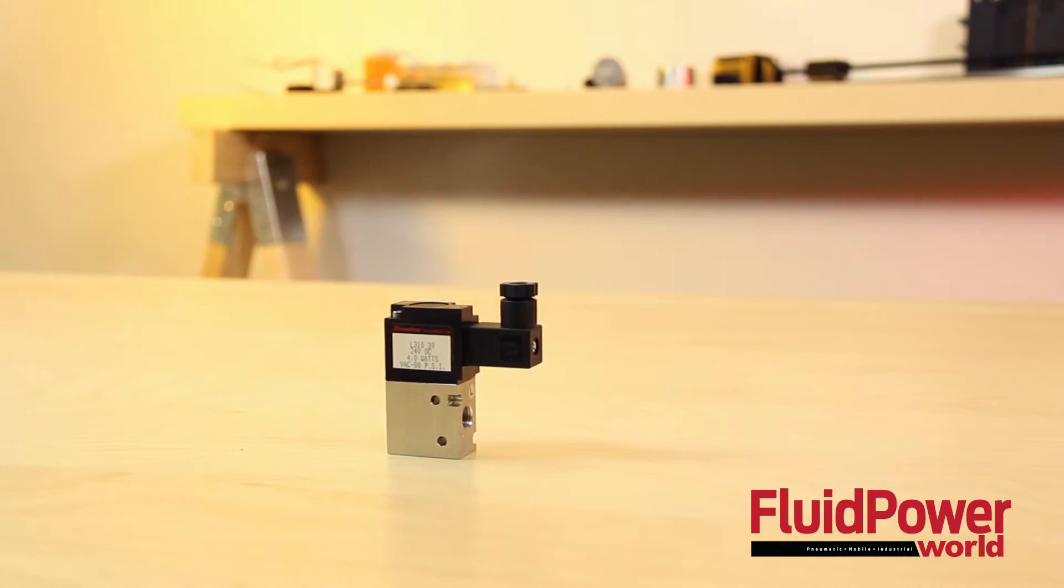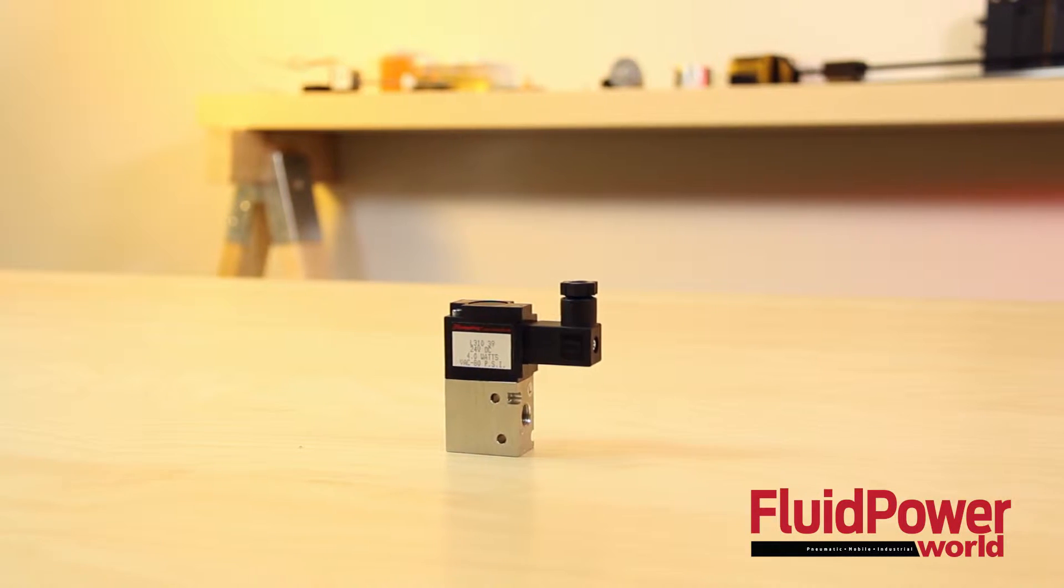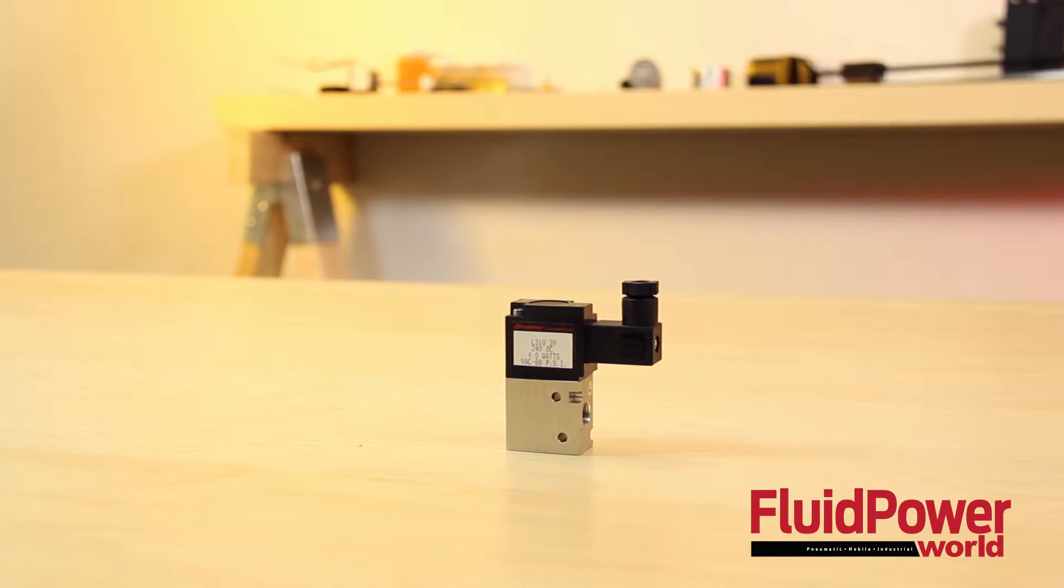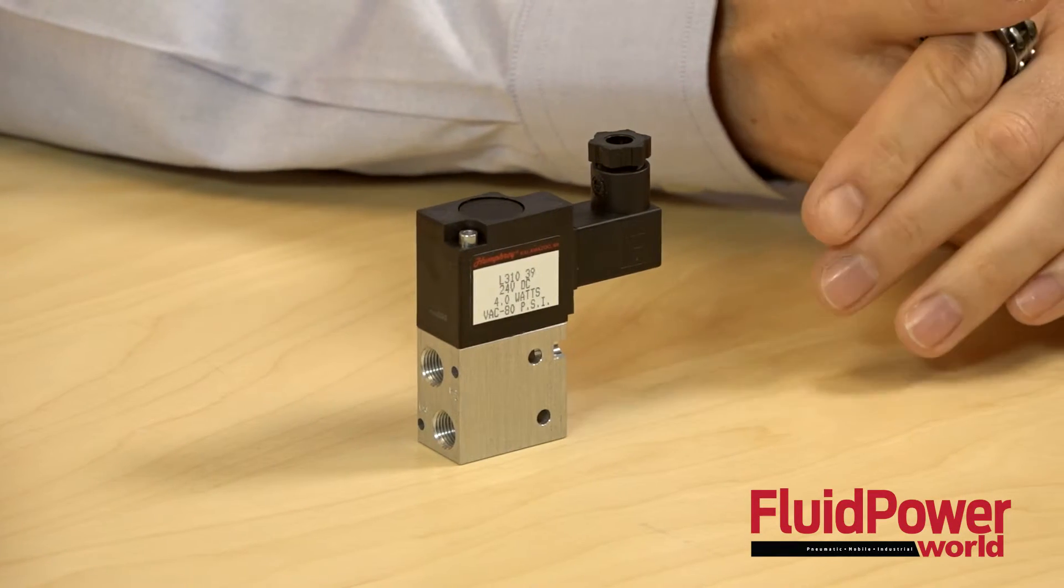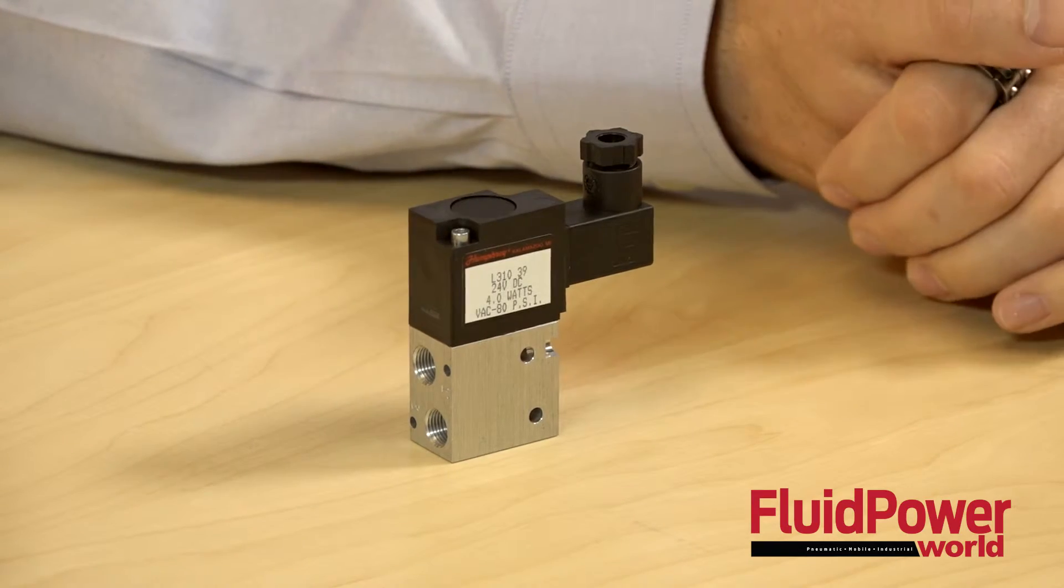Standard single solenoid valves require electrical power while holding the valve in the energized position. But here, a 50 millisecond pulse of the solenoid fully shifts the L310 from one position to the other. Power is removed and the latching function holds the solenoid in valve position and that offers significant energy savings.